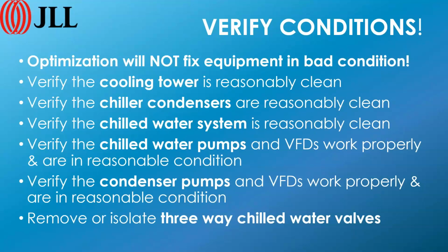Same thing with condenser pumps and VFDs. You want them to work properly and be in reasonable condition. And on the chill water side, we want to remove as many chill water three-way valves as you can. Either remove them or isolate the bypass leg. That's because we don't want a lot of unused chilled water pumping out of the chiller plant and coming back. Any water going out of the chill water plant, we want to be using for cooling purposes. Now you may come across situations where you have one or two three-way valves at the end of a loop. That's no big deal. You can leave them in. One or two here or there isn't going to break the bank.